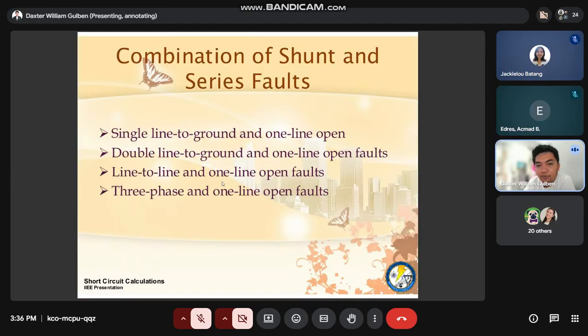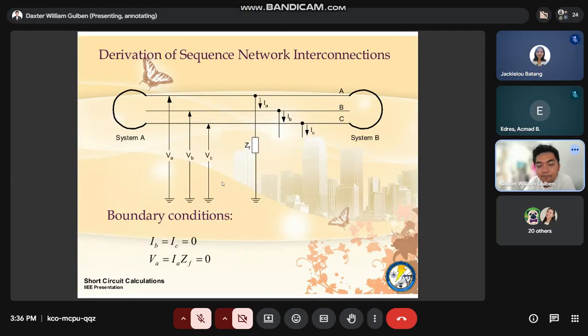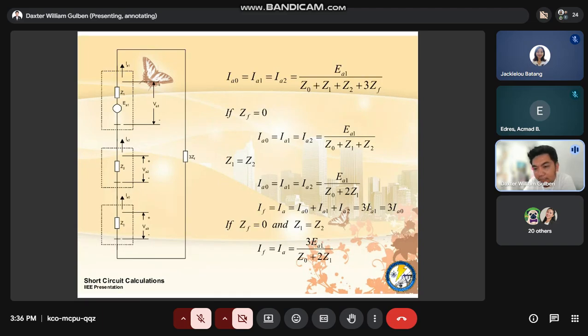So basically, 3 times of the same values man sila. 3 times the IA1 or 3 times IA2 or 3 times IA0. Parehas lang gyapon sila nga values. So therefore, your I fault for a single line to ground is equivalent to 3 times the IA1. Basically, kining EA1 gitawag nga pre-fault voltage. Later, atong discuss nga unsay value.